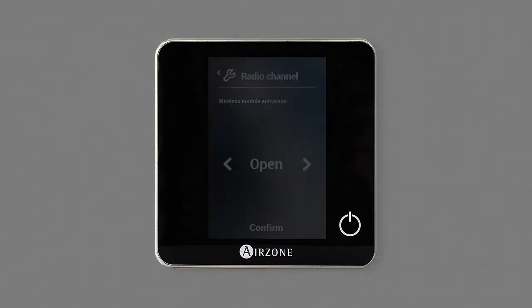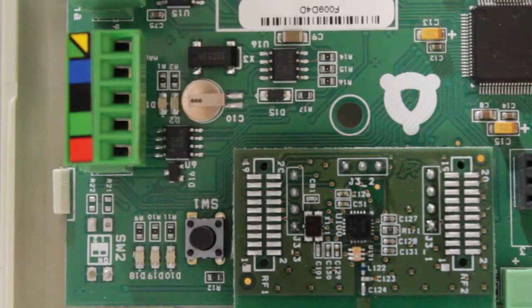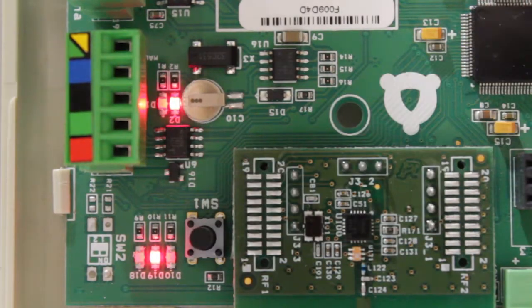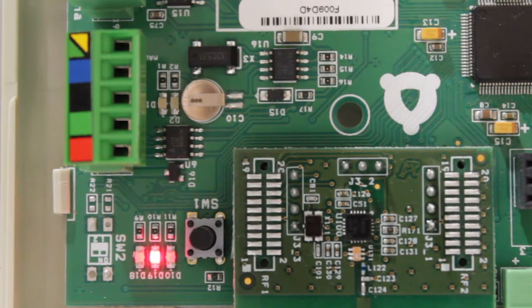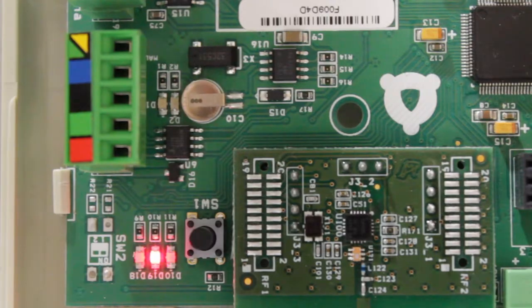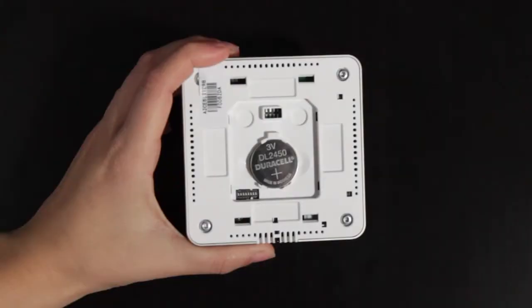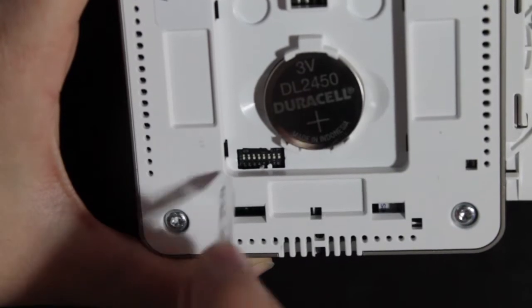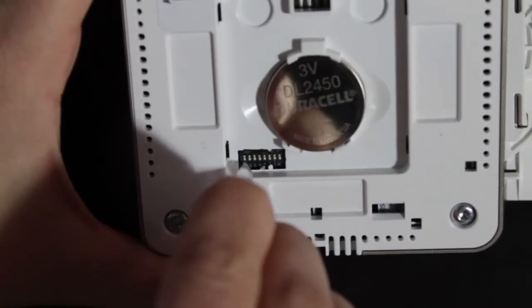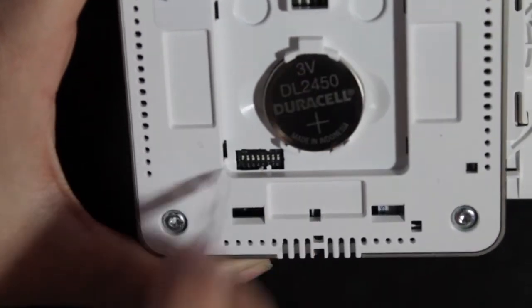Press briefly on the association button. The LED D19, located next to the button, will show a steady light indicating that you can start the association process. Set the zone address by using the tool supplied to move the micro switch to the on position.